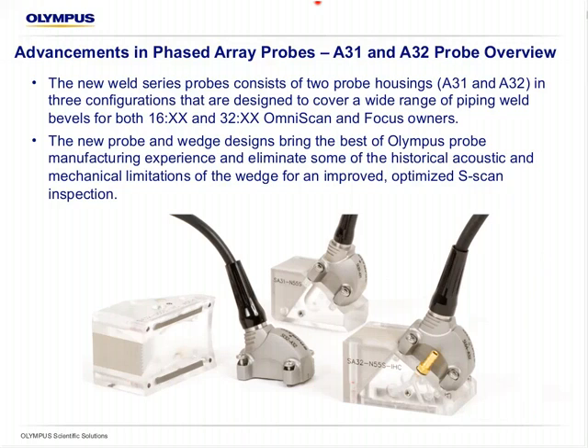The new Weld series probes from Olympus consist of two new probe housings, the A31 smaller pitch, smaller probe, and the A32 larger probe. These are in 3 configurations that are designed to cover a wide range of piping bevels for both 16 pulser instruments like the OmniScan SX and 32 pulser instruments like the MX2 and Focus. The new probe and wedge designs bring the best of the history of Olympus probe manufacturing and eliminate some historical acoustic and mechanical limitations of the wedge for an improved optimized S-scan inspection.